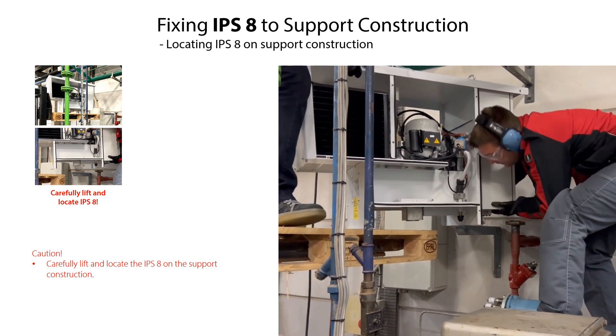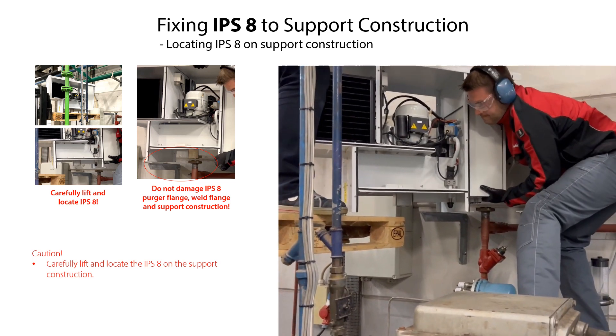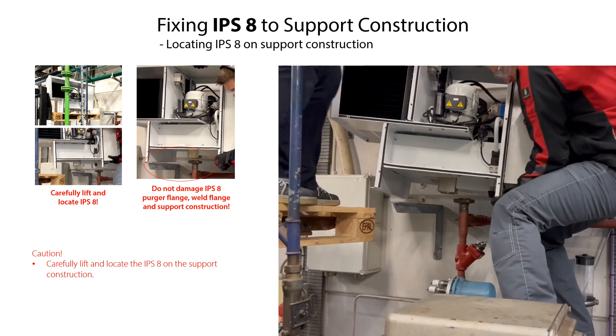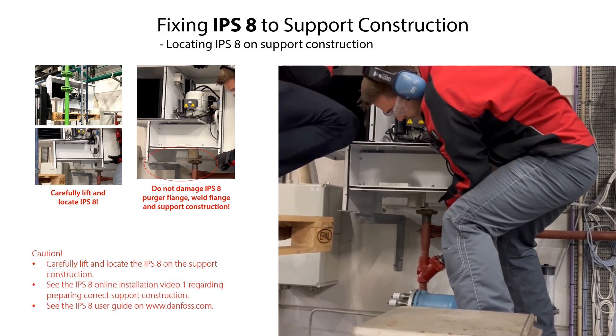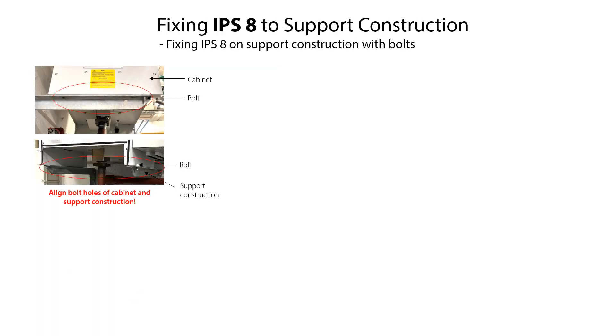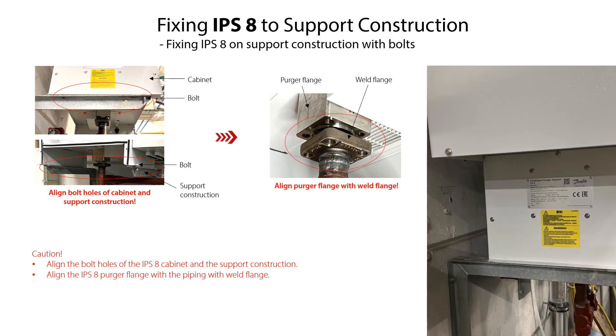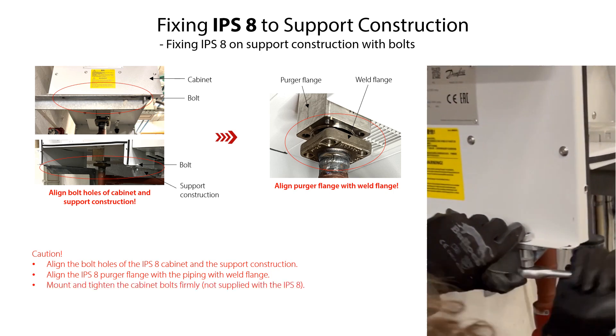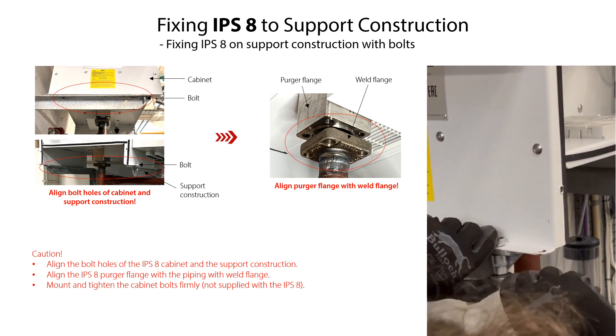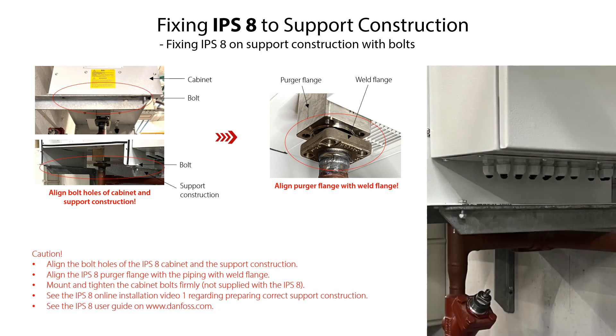Carefully lift and locate the IPS-8 on the support construction. Be careful not to damage the IPS-8 unit, the IPS-8 purger flange, the piping with weld flange, and the support construction during the lifting and location of the IPS-8. Once the IPS-8 is located on the support construction, ensure that the bolt holes in the IPS-8 cabinet are aligned with the bolt holes in the support construction. Also ensure that the purger flange is aligned with the piping with weld flange. Then mount all the IPS-8 cabinet bolts and tighten them firmly. Please note that these cabinet bolts are not supplied with the IPS-8.